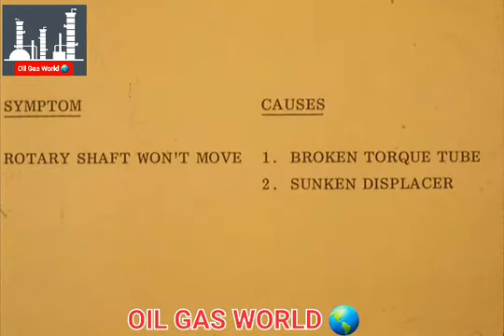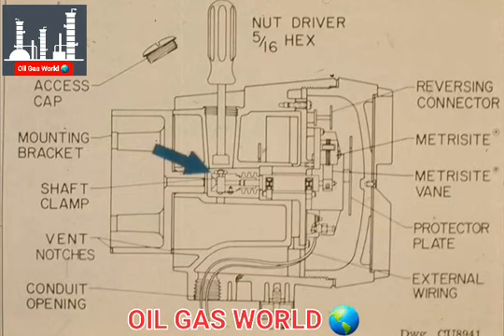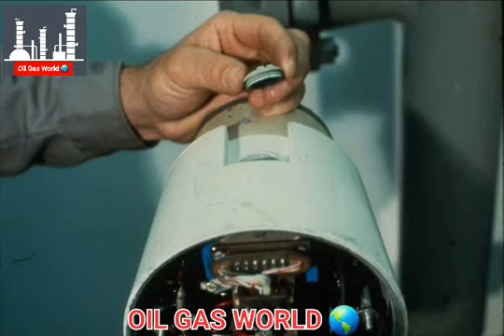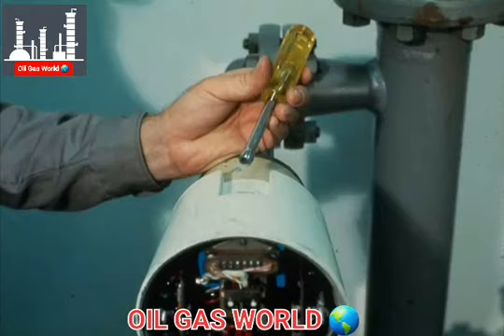Suppose the rotary shaft didn't twist. What would you assume? The torque tube could be broken. The displacer could be sunk. Or the shaft clamp nut could be loose. The shaft clamp connects the torque tube rotary shaft to the input shaft assembly. To check the clamp nut, remove the access cap. Loosen the clamp nut with a 5/16 of an inch hex nut driver.